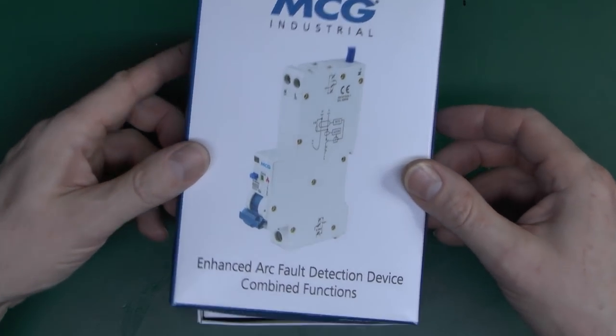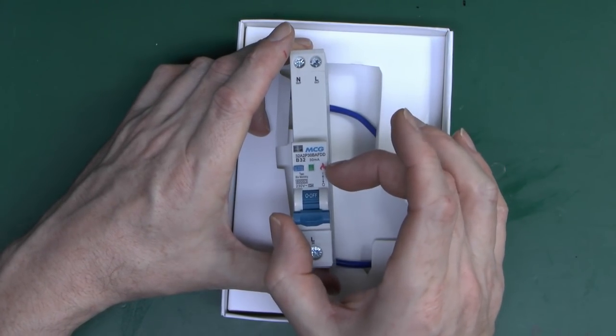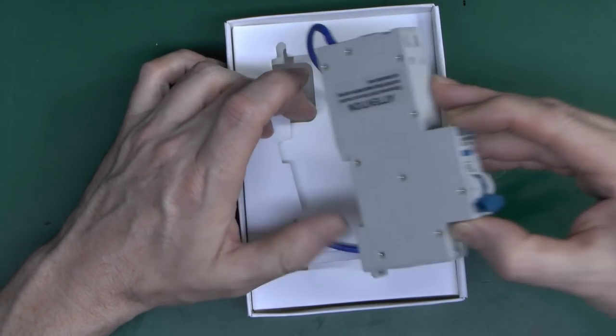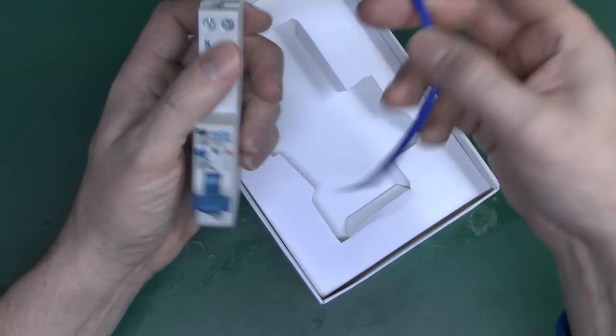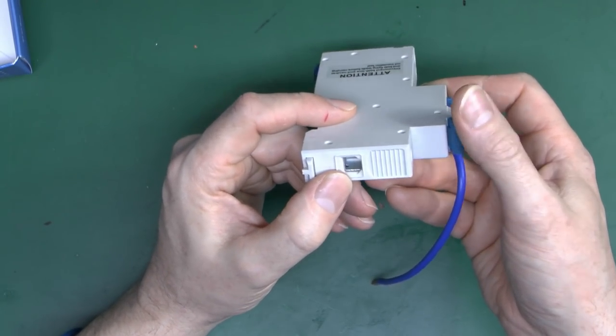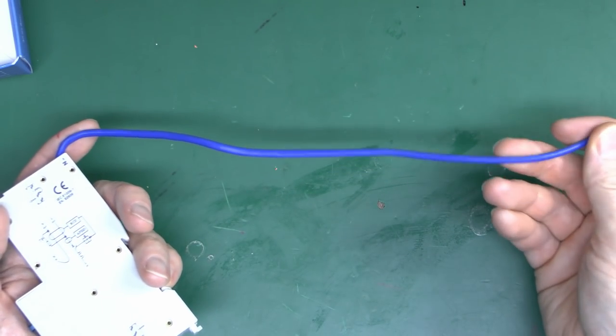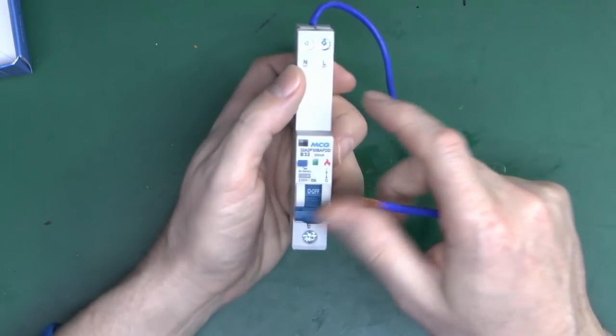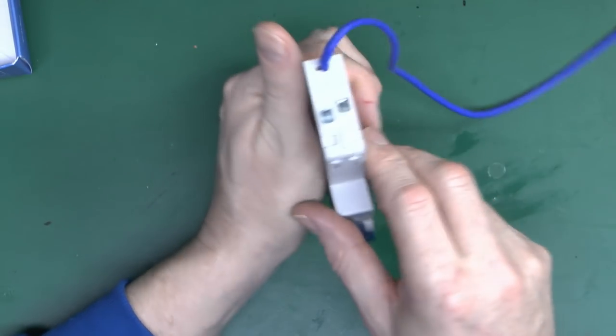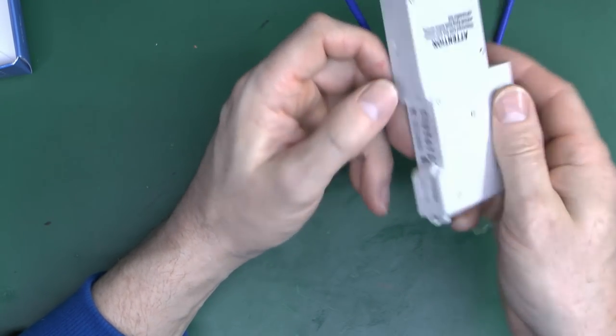This comes in a fairly large box. In terms of dimensions, it's a single module wide, but it's actually a tall module, similar to the older type RCBOs. So let's take it out of the box. It's a fairly usual arrangement — line in at the bottom, neutral in via the flying lead which is about 12 inches long, fine for a consumer unit but not necessarily for a large distribution panel. Circuit wiring connections on the top with line and neutral terminals, and it clips onto the standard rail at the back.